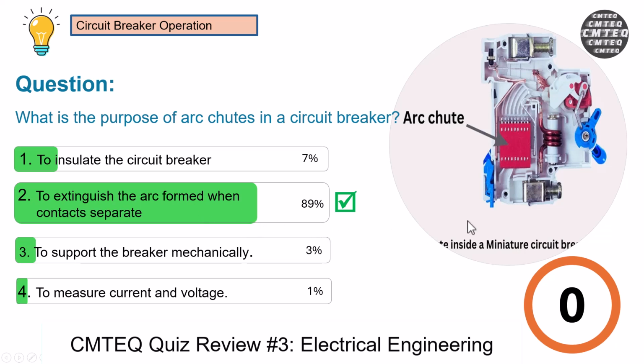But why is this the correct answer? This is related to the internal working principle of the circuit breaker. What happens inside the circuit breaker when the contacts open under a load, because it wants to interrupt a short circuit current, a high current, maybe an overload? An arc forms between the two contacts as they separate, and that is caused by the ionized air inside the circuit breaker.